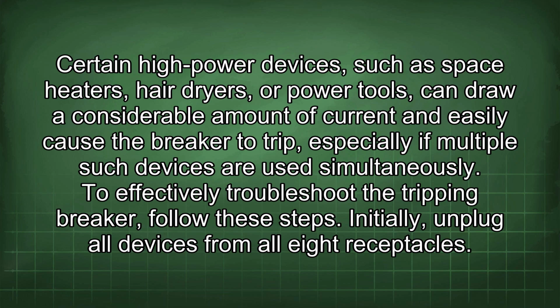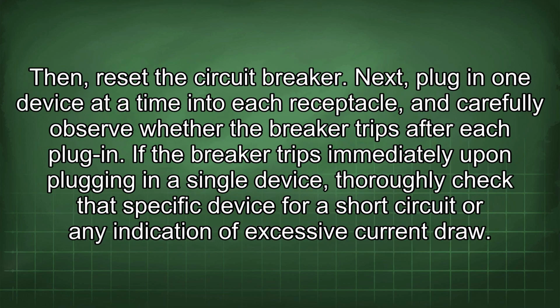To effectively troubleshoot the tripping breaker, follow these steps. Initially, unplug all devices from all 8 receptacles. Then, reset the circuit breaker. Next, plug in one device at a time into each receptacle and carefully observe whether the breaker trips after each plug-in. If the breaker trips immediately upon plugging in a single device, thoroughly check the specific device for a short circuit or any indication of excessive current draw.